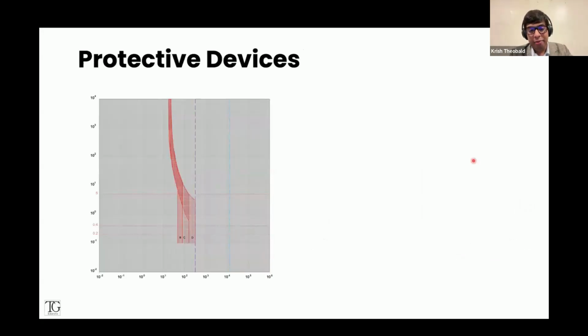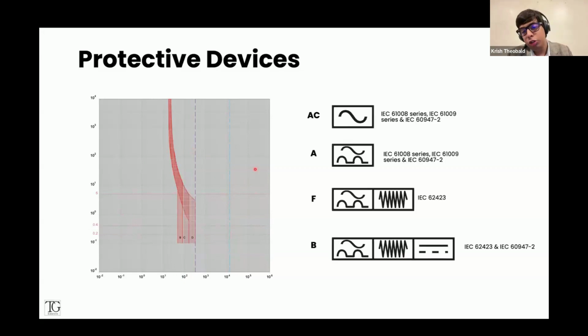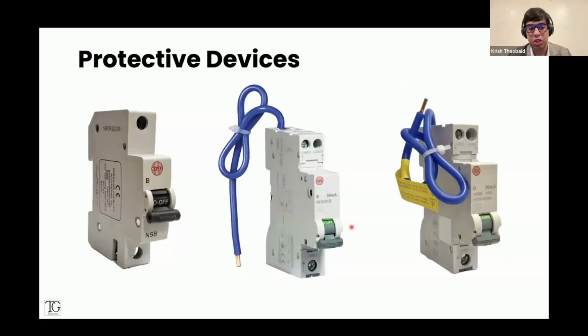We've got the MCBs that we generally use, or we also have circuit breakers like your MCCBs and fuses. These have certain tripping characteristics. And we've got your RCDs. So, overcurrent protective devices and residual current devices. Now, we know that there are the AC, A, F, and B types, but we shouldn't be using the AC. So, these are the protective devices we should be using.